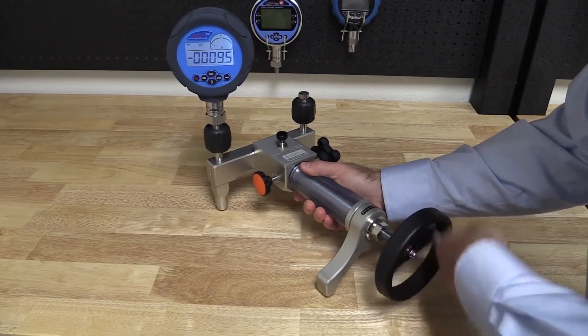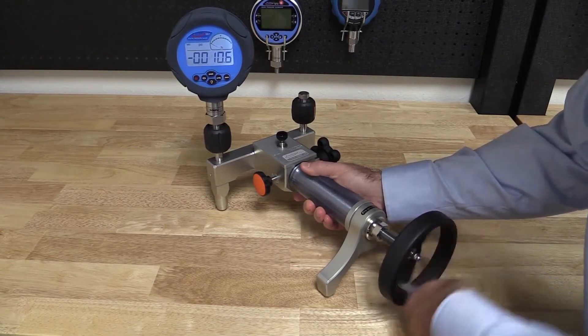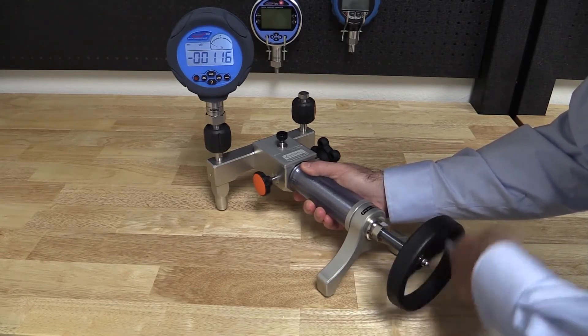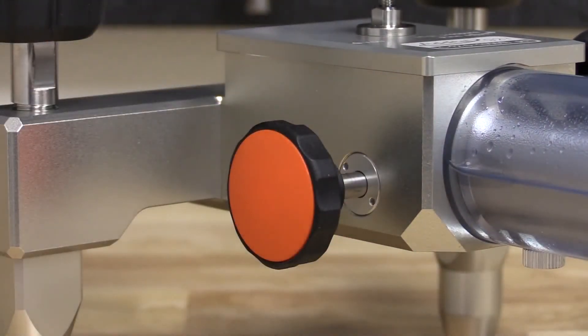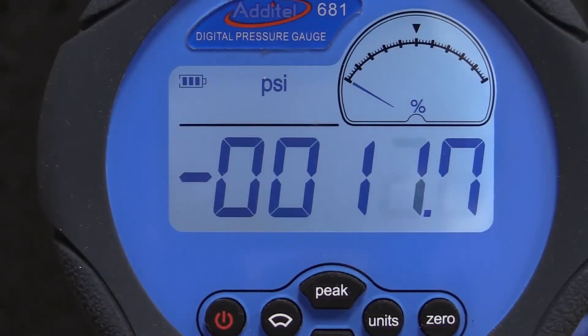You'll notice a slight vacuum being pulled on your reference gauge. The strength of the vacuum can be a good indicator of the amount of gas in the system. Now that we have a vacuum pulled on the system, we will open the vent valve and let fluid fill into the system. You'll notice this by the gauge settling to zero.